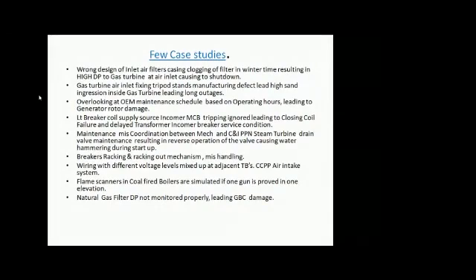The same thing happened in the Gulf where I worked. The tripod stands, which are supposed to be used for holding the filters, had supports that were not properly manufactured. Because of that, sand ingression was happening inside, and because of the sand ingression into the gas turbine, the turbine blades and compressor blades were getting fouled. The machine had to be shut down frequently for inspection, and it caused a lot of damage also. This is an engineering or quality issue. The engineering was done properly, but the quality failed. They didn't check the quality of the material supplied by the OEM.